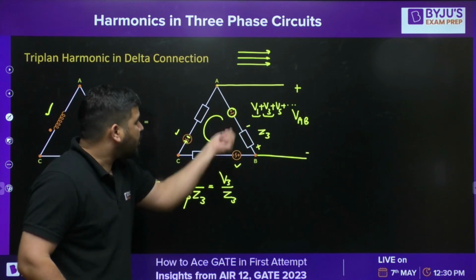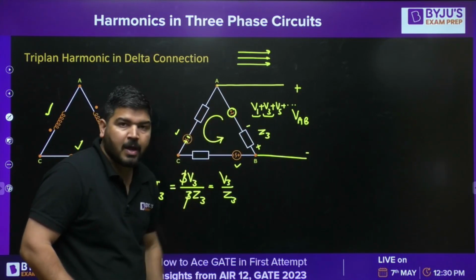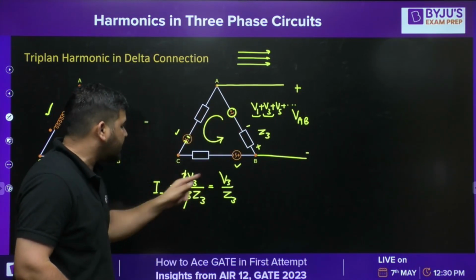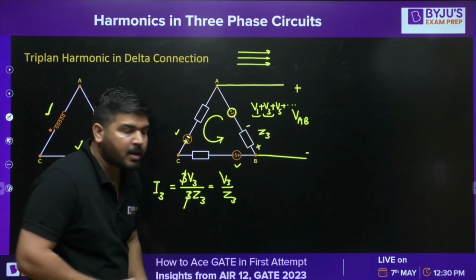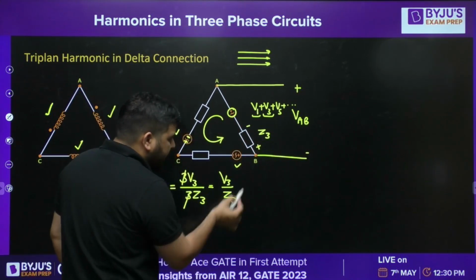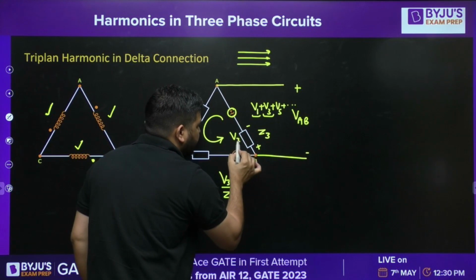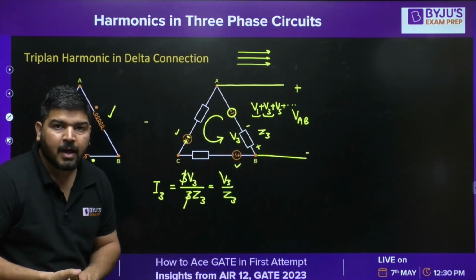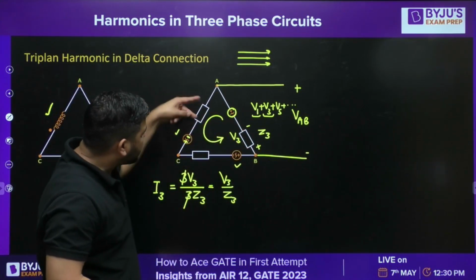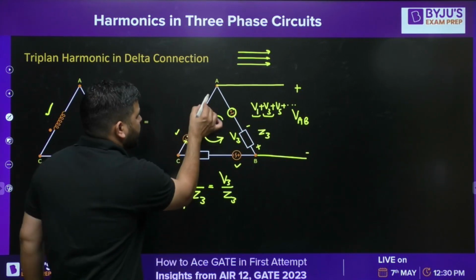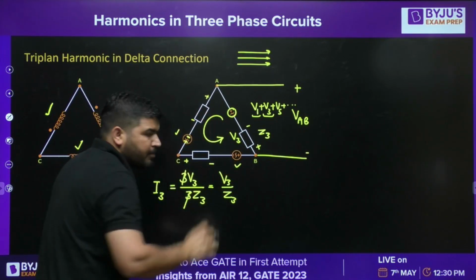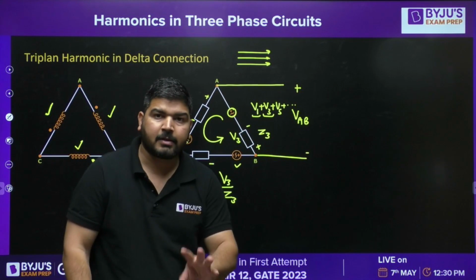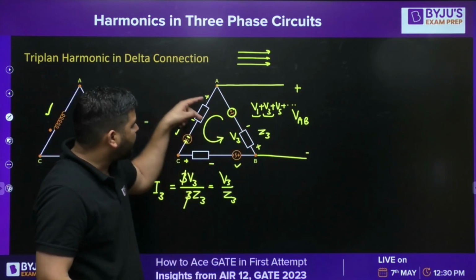So if there is a third harmonic component of circulating current, this drop will be the circulating current into Z3. So if you multiply this circulating current with Z3, you will get the voltage as V3. It means across these impedances, you have the voltage. Across these impedances, you have the voltage—it's not induced actually, you have the voltages.